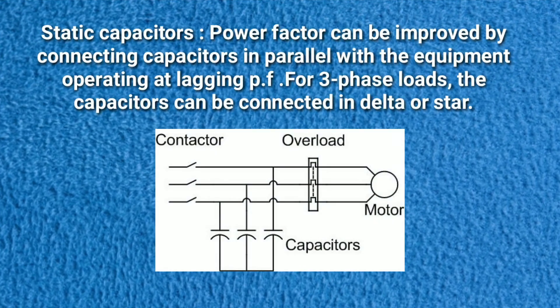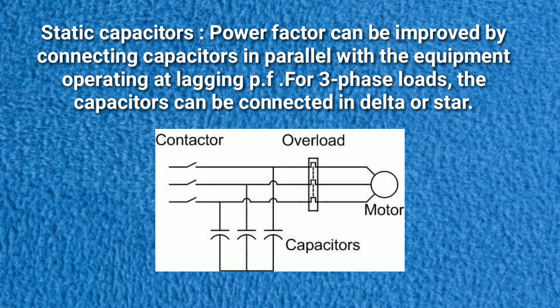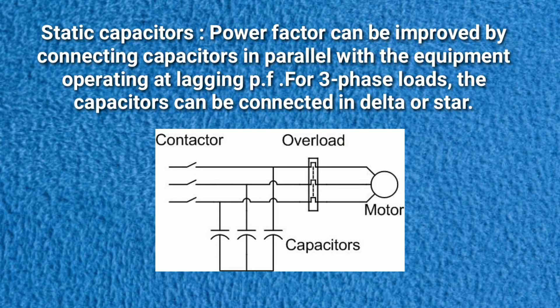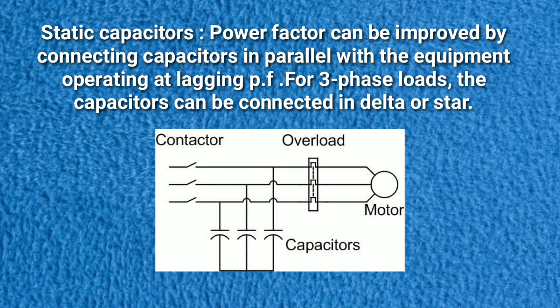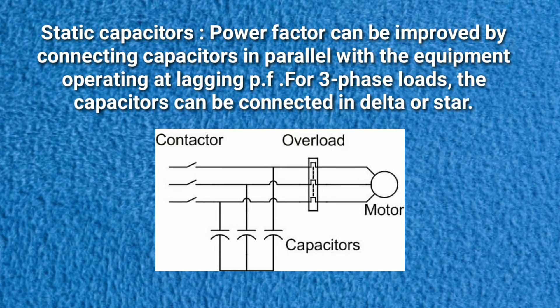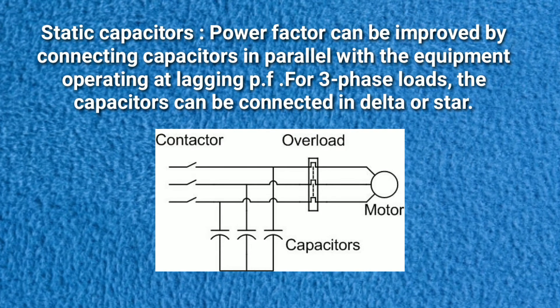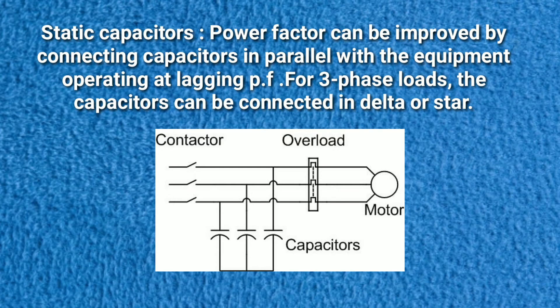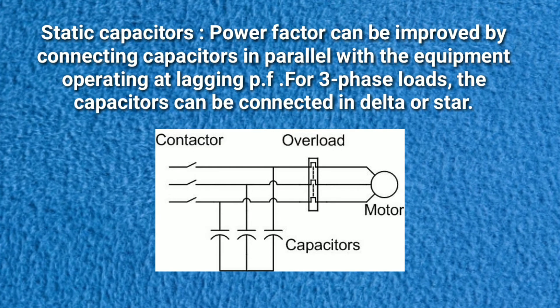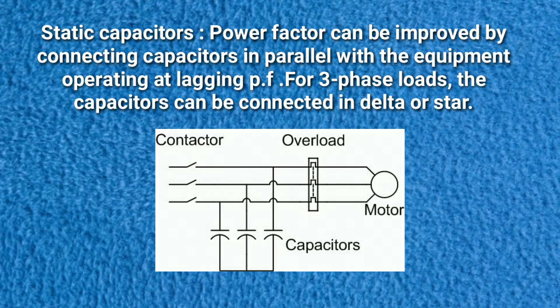With the following equipment, power factor can be improved. Static capacitors: power factor can be improved by connecting capacitors in parallel with the equipment operating at lagging power factor. For three-phase loads, the capacitors can be connected in delta or star.